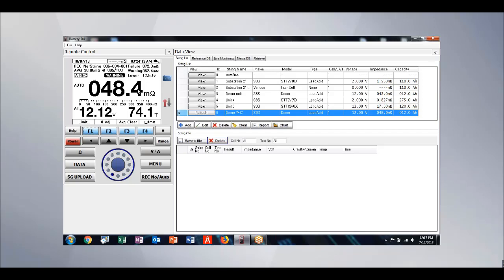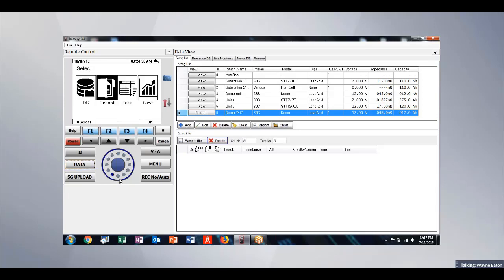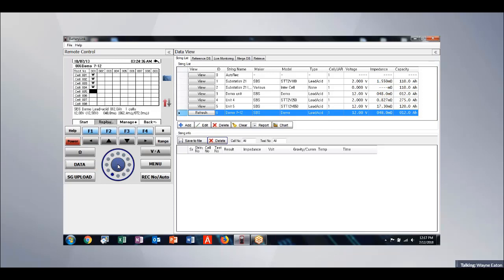Let's say I'm going through my string and all of a sudden I get my leads backwards and I get a bad reading. Here I've got a reverse polarity. It's showing up at minus 12.21 volts. With our unit, I can actually go back into data, into that data record, into that demo string. I can go back up 1 space to that recording that's in error. It was recorded at minus 12.2 volts. I can press the start button, and then I can read and record back over top of that previous reading.